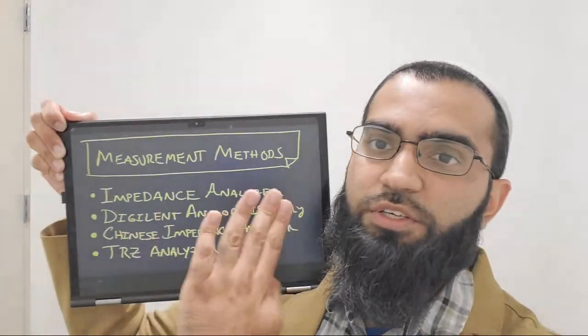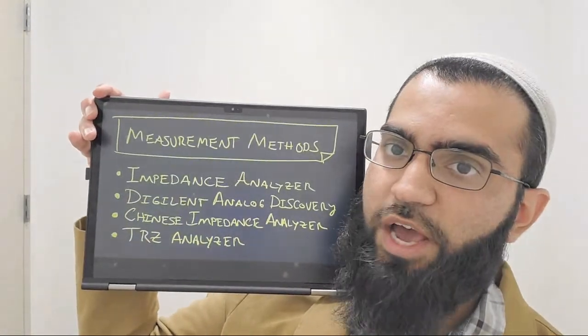So impedance analyzer, I guess the holy grail, the Agilent or the HP, which became Agilent, which became Keysight, that is the standard. If your company can afford such products, they should purchase them if they're going to be working in the area for a long time. They're very accurate. Quite frankly, they're the standard of measurement. They're calibratable as you'd expect, and they have a lot of functionality in order to get you accurate measurements. So it is a valuable test instrument for measurement of impedance. But the question was asking for the cheapest one.